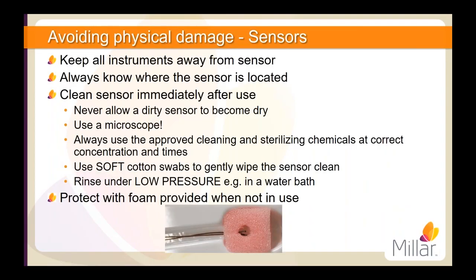To avoid damage to the sensor, it's important to always be mindful of where the sensor itself is located and to keep instruments, etc. away from this area. This includes when the catheter is inserted into a vessel. Care should be taken to avoid squeezing the sensor area through the vessel wall, either with forceps, fingers, or suture threads. The sensors should be cleaned immediately after use. If they cannot be cleaned immediately, then they should be placed in saline or water immediately after removal from the vessel so that they do not dry out, as this makes it very difficult to get them clean.